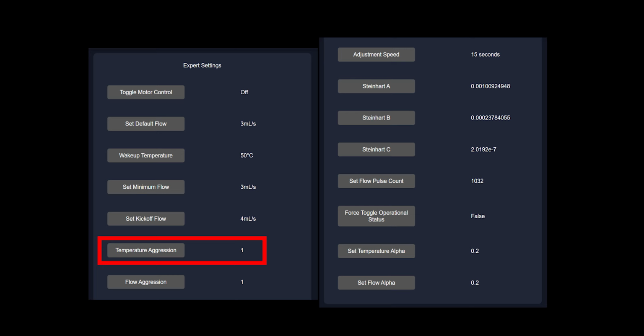The temperature aggression is a number that multiplies how large a correction is. For example, if ATACC decides it needs to make a correction and reduce flow by a value of 2, if the aggression is set to 1, then the correction will stay at 2. But if the aggression is set to 1.5, then the correction will be 3. Or if the aggression is set to 0.5, then the correction will have a value of 1. Flow aggression is the same thing. ATACC will check what the target flow is and compare it to the actual flow. It will make corrections based on the difference between the target and actual. This flow aggression simply multiplies that correction.